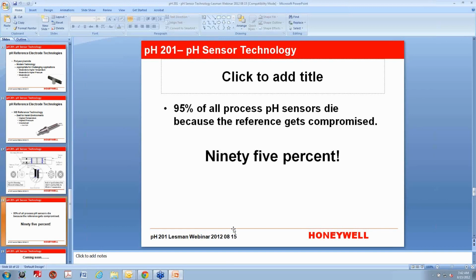But here's the deal. 95+% of all process pH sensors die because the reference gets compromised. 95% is a lot, which is why you don't see very different measuring electrode technologies, but you see a lot of different reference electrode technologies, because the reference electrode is the weakness in pH sensors. And so that's what manufacturers have gone after over time. And this HB technology is a patented technology.